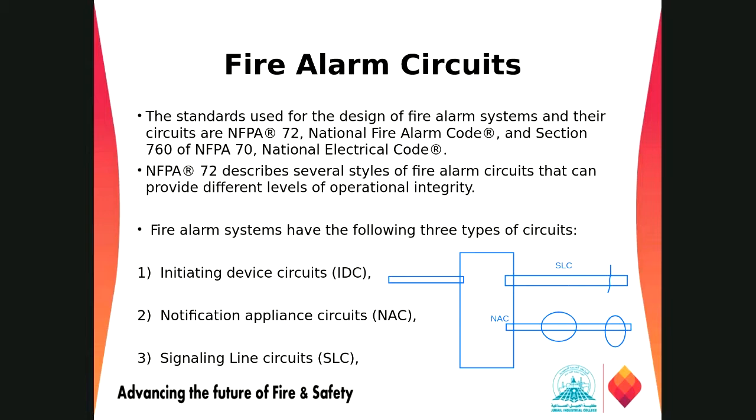SLC is used for addressable alarm systems and addressable control panels, and the IDC is used for the conventional one. Also, we can use IDC in the addressable or intelligence system just for supervisory purposes.